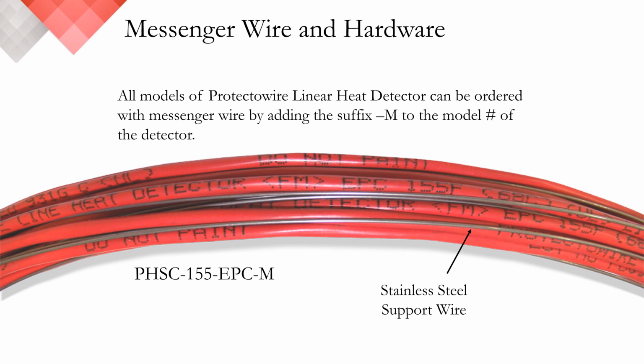As shown here, messenger wire is available with any model detector on special order. It consists of high tensile strength stainless steel wire which is wound around the detector at the rate of approximately 1 turn per foot, or every 0.3 meters. It's a carrier or support wire which is designed to simplify the installation of the detector in areas where mounting is difficult due to either lack of appropriate support structures or mounting surfaces.